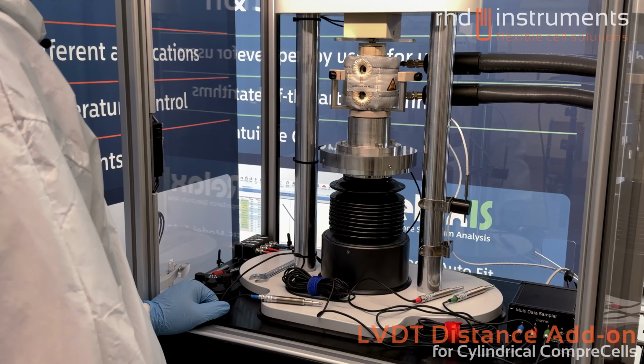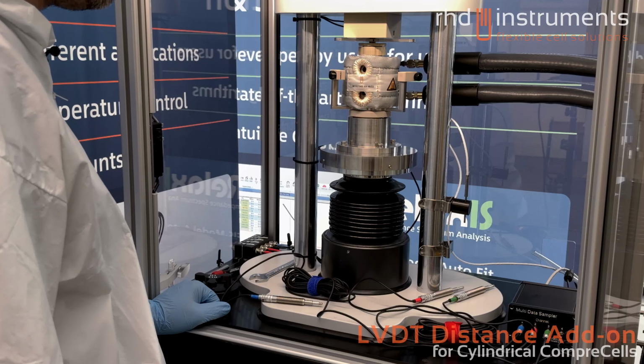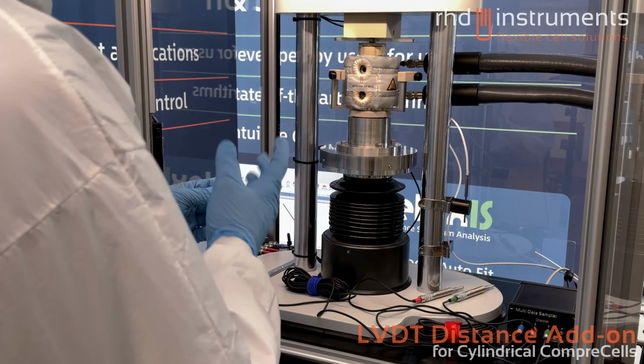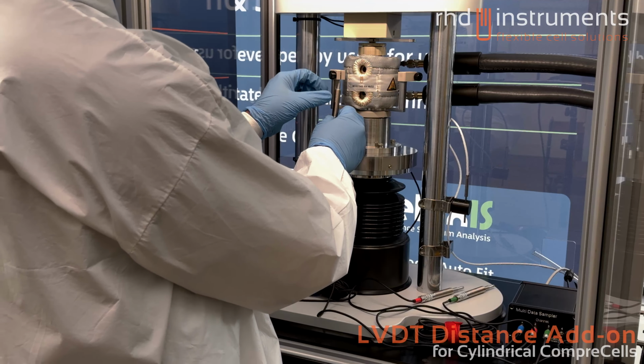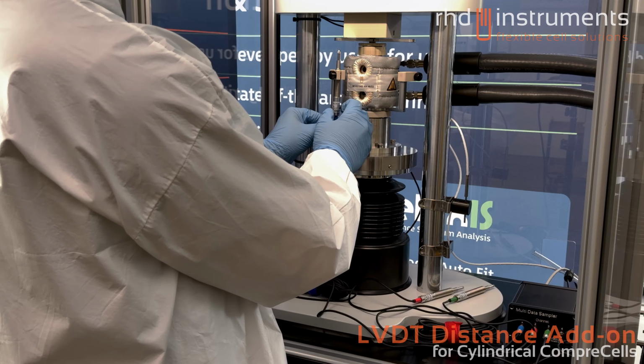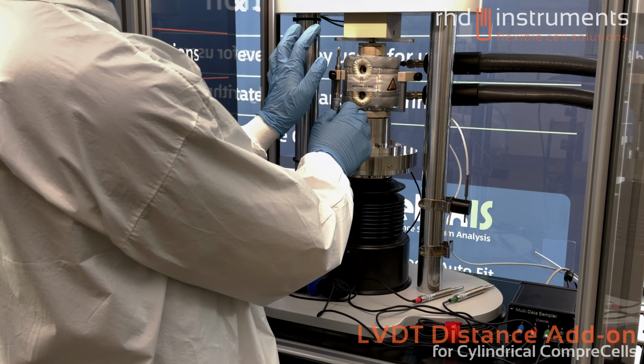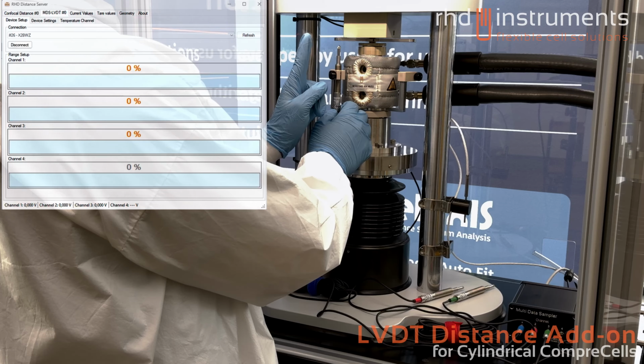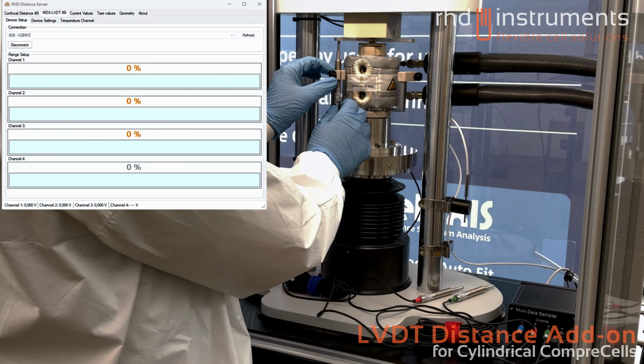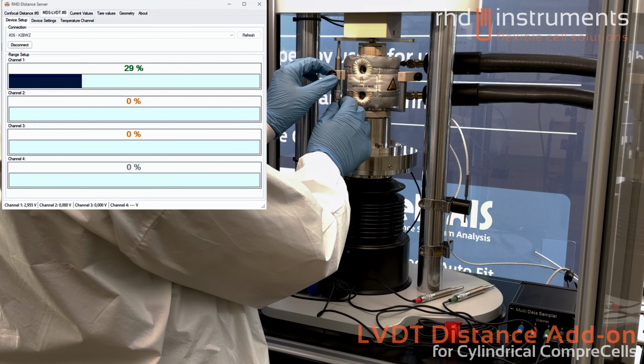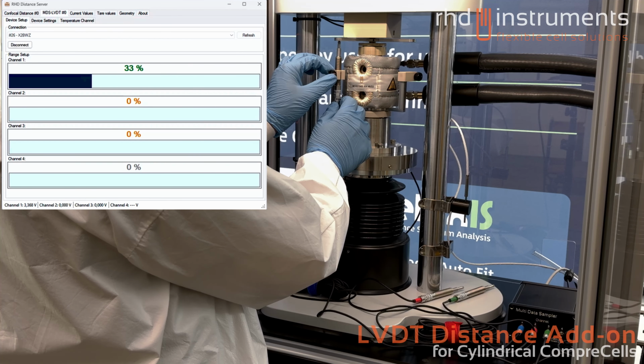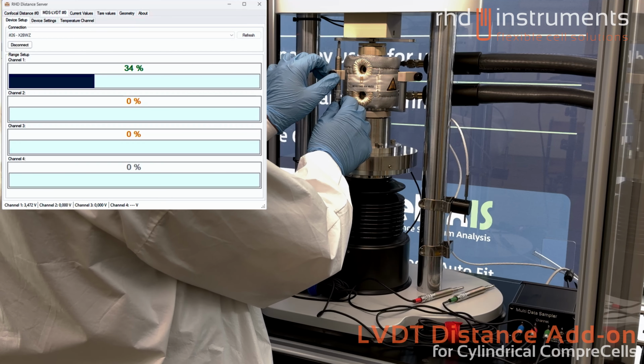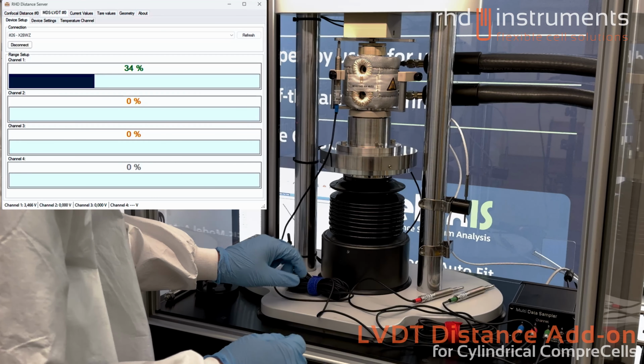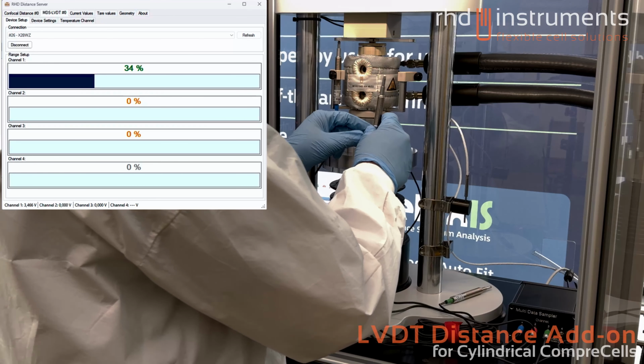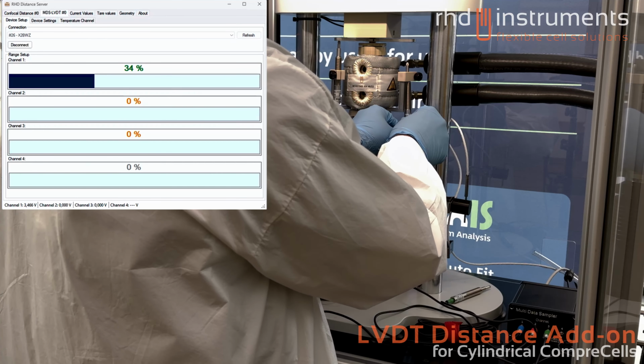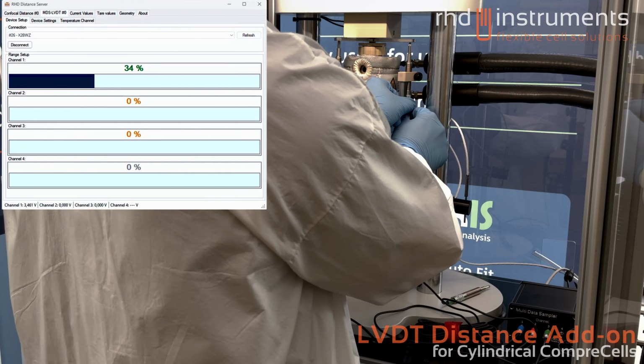Next, we want to mount the sensors. I have already connected my 3 sensors to the multi-data sampler, and I will start with the sensor on channel 1. It doesn't really matter because they are all equivalent. I will insert the sensor from the bottom here, and when the sensor touches the cantilever, please make sure that it only touches the insulated center part. During the mounting process, we want to monitor the sensor signal on the computer to make sure that we don't exceed the working range. And when we have adjusted the sensor to a deflection of approximately 30%, we can fix it in place. I will repeat the same process with all 3 sensors.